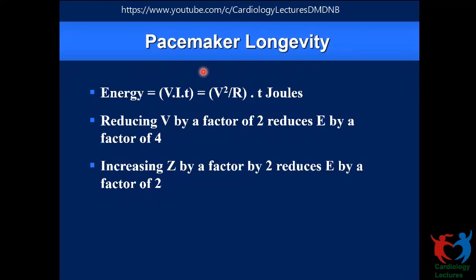But there is another resistance which is called a polarization resistance. In polarization, what happens is, imagine you are pushing electrons through the wire to the lead tip, which is a negatively charged particle, which attracts a lot of positive ions at the lead tip. Now, as the positive ions accumulate at the lead tip as you are delivering the output, it is surrounding the lead tip. Now, if you want to make more electrons flow out of the tip, ideally you want to increase the surface area of the tip electrode, so that the accumulation has some gap so that electrons can go out. But if you increase it too much, then your pacing efficiency is not good.